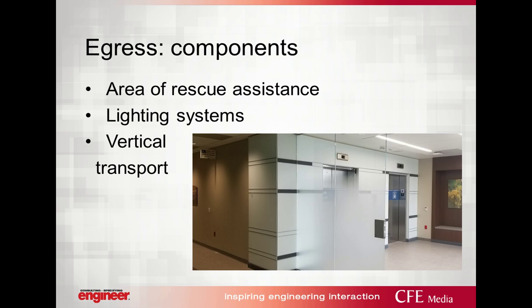Now, egress within our building is important. We have to take into consideration our elevator lobbies, and if our elevators are going to be used for evacuation during a fire, we have to, A, have an enclosed lobby for them as required within NFPA 101, and additionally, we will remove the sprinkler shunt trip controls. Now, that's important for designers and engineers to understand. We're so used to putting shunt trip on elevators, but if we're going to use them for fire rescue, we can't do that. All these egress components will come into play through NFPA 101 as well as elevator code. Now, Rick's going to go a little bit more in detail about elevators for us.